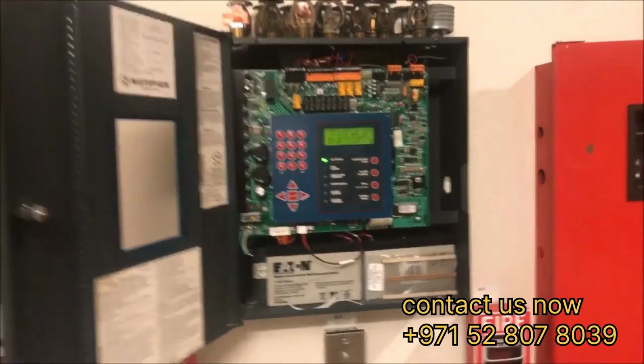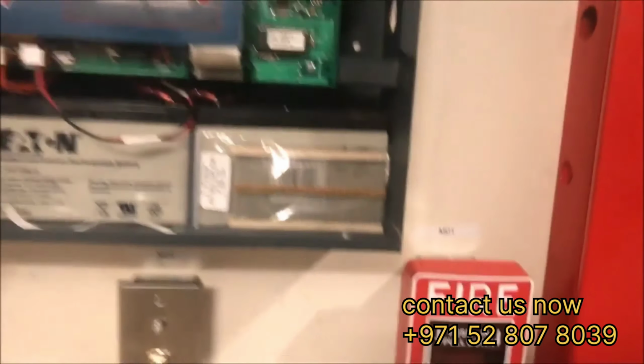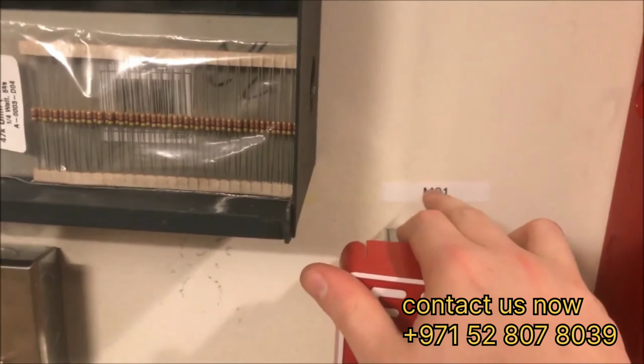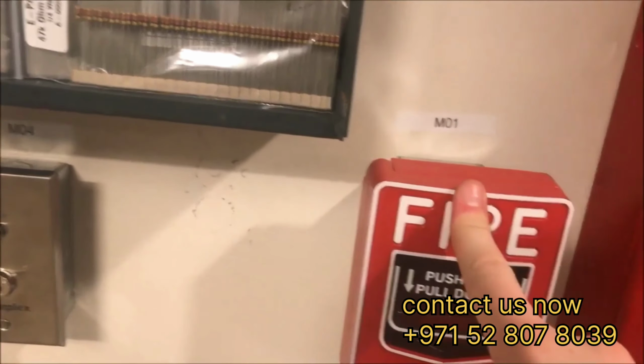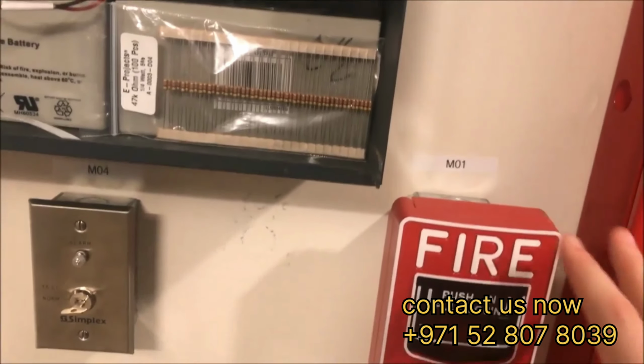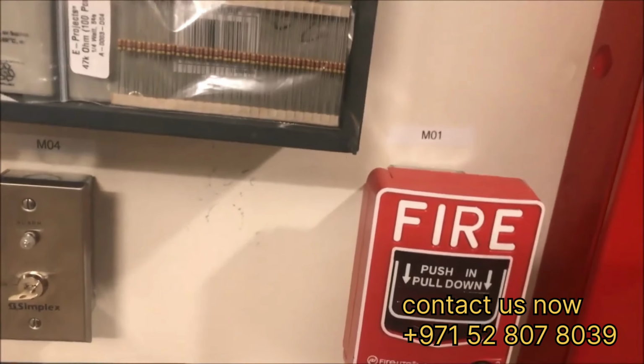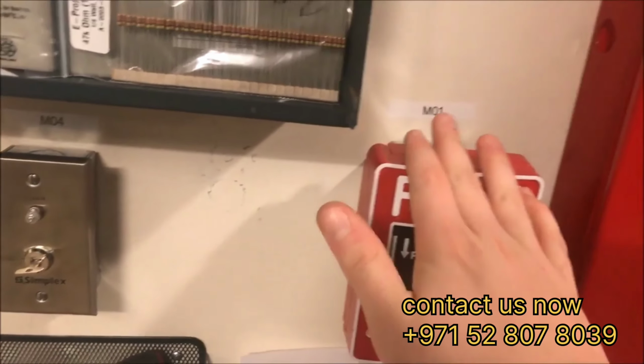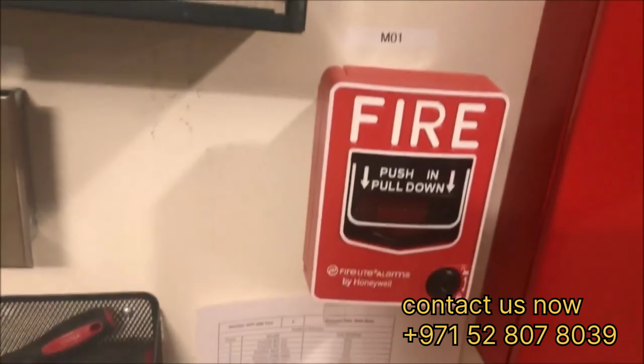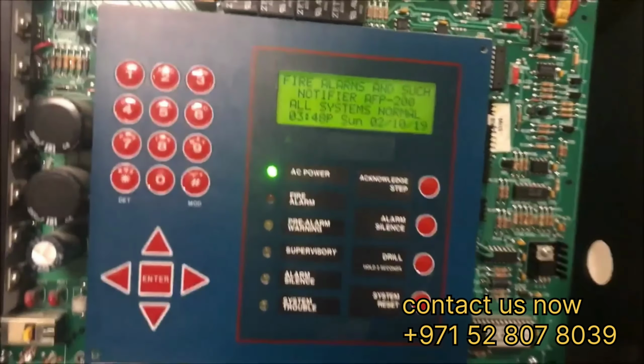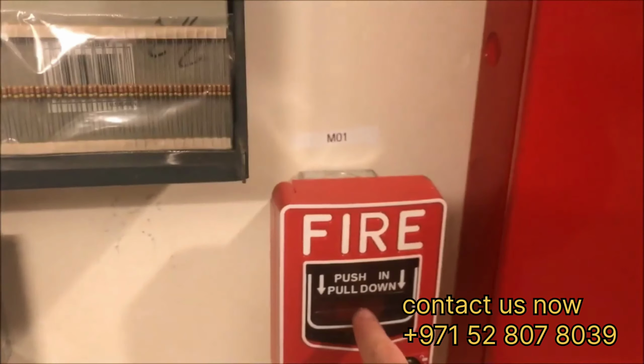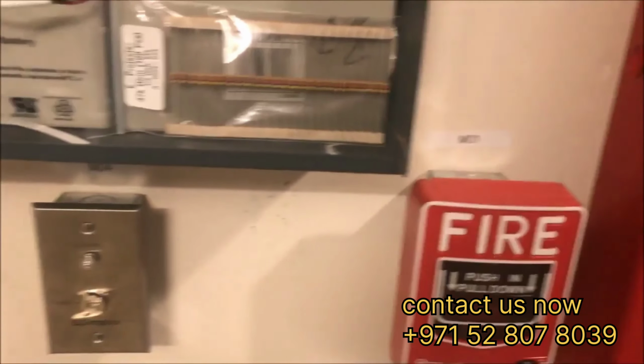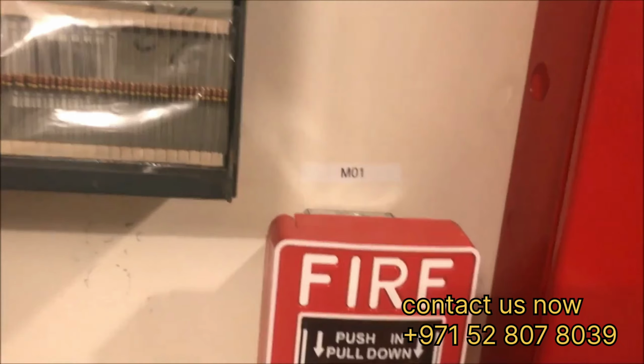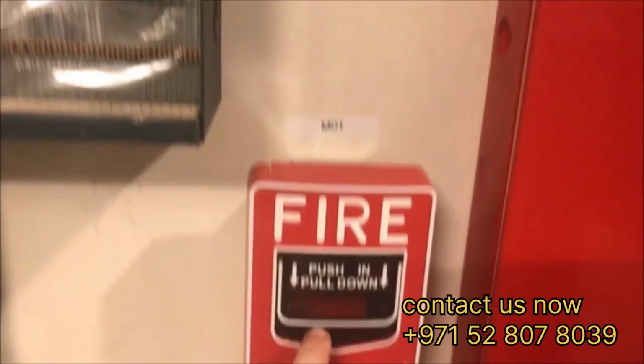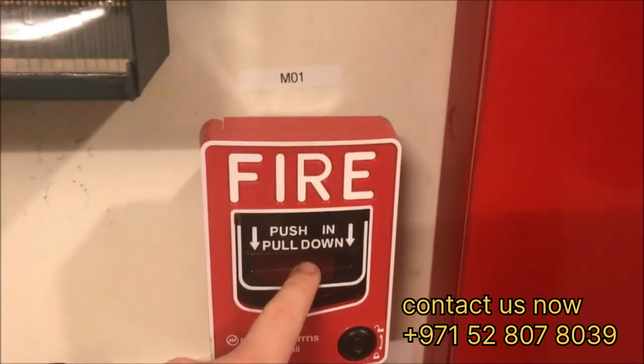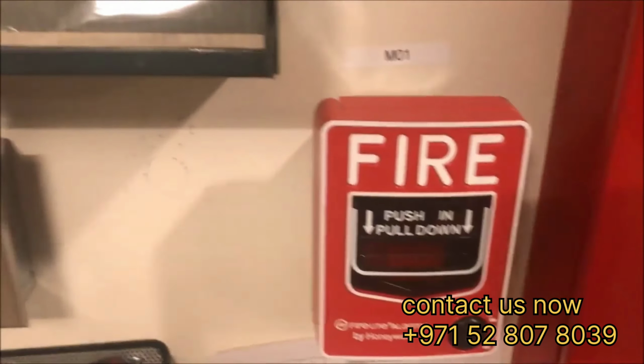So the way that this would work is you can see I have M1, or just M01. So this is point 1. This isn't like a zone. There's only one device, not a whole area of devices or chunk of devices, just one device that is number 1. So if you pull it and it comes up on the screen as point 1, you know it is exactly this pull station. Not, oh, it could be one of the pull stations on the 3rd floor. No, it's pull station 1, which is on the 3rd floor by the west stairwell. You know exactly where it is.